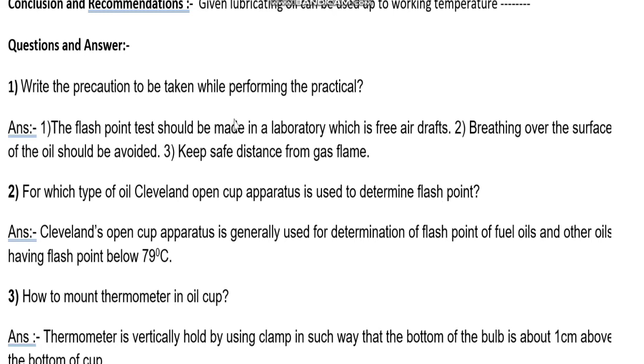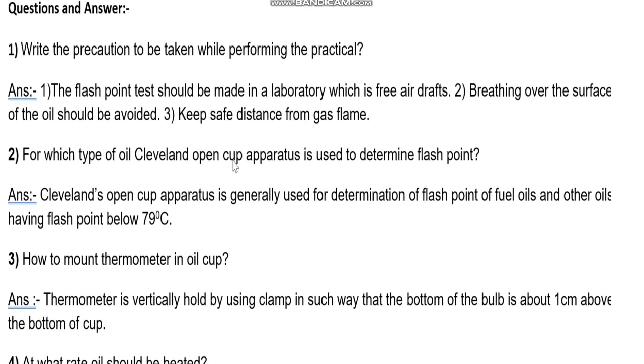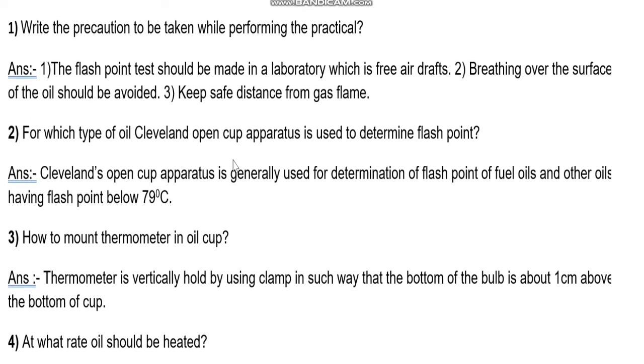Precautions: first, the flash point test should be performed in a laboratory that is free of forced air. Breathing over the surface of the oil should be avoided. Keep a safe distance from the gas flame.